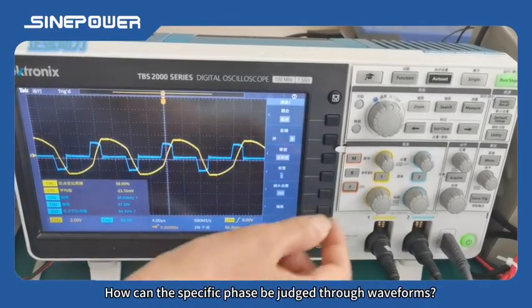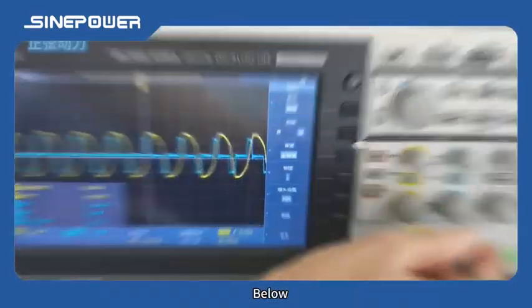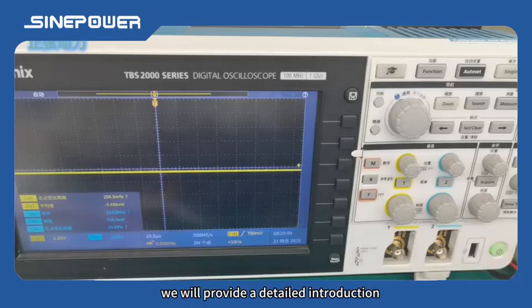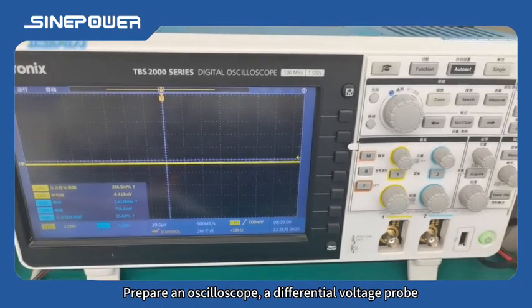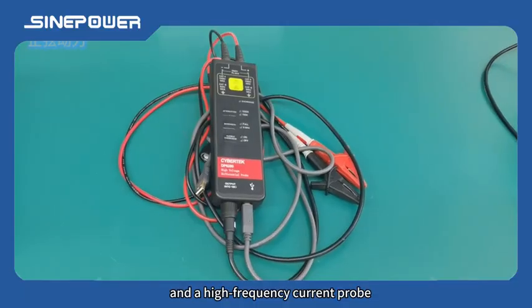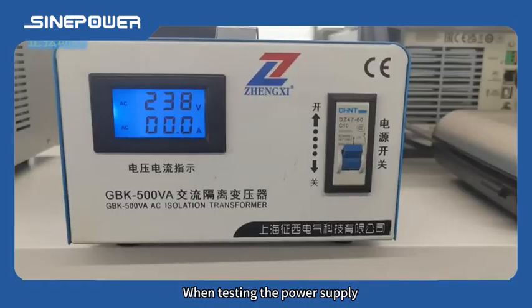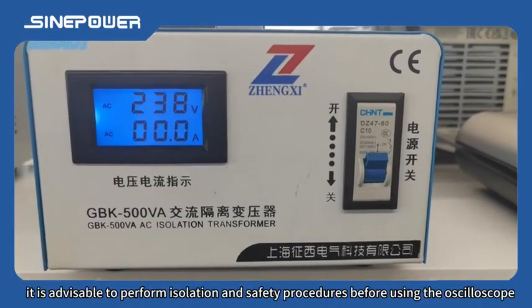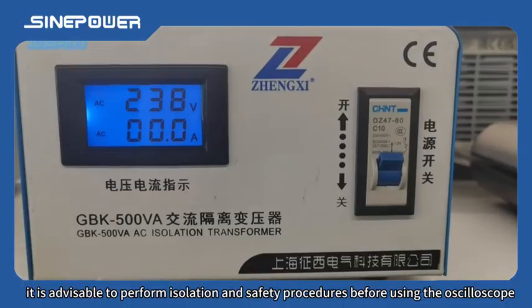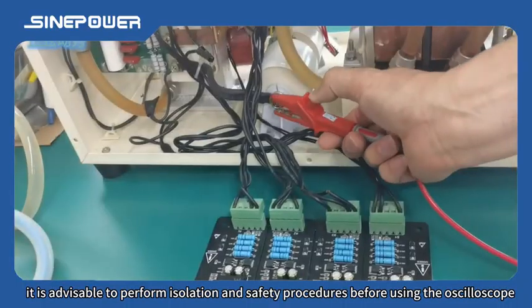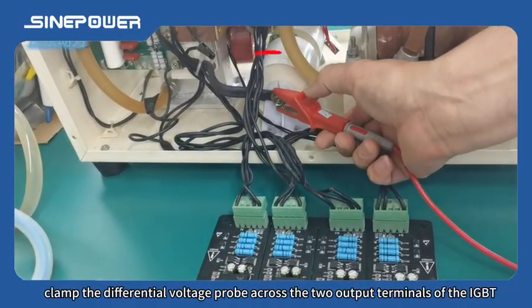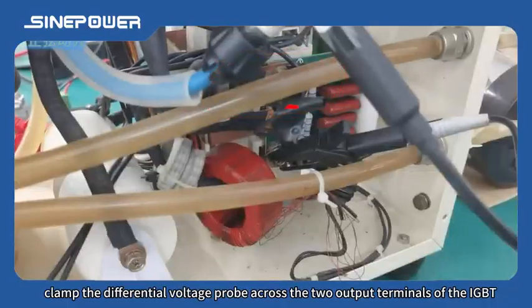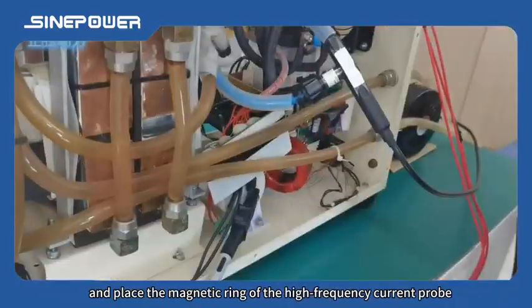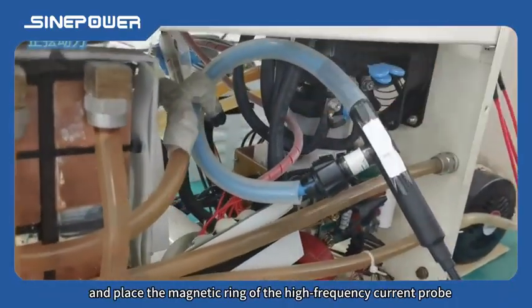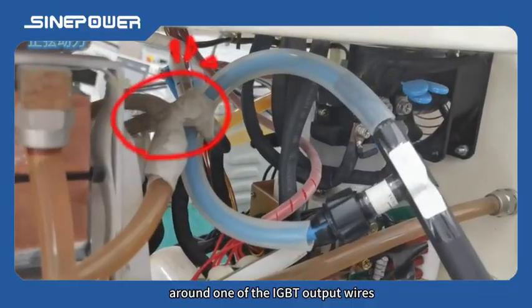How can the specific phase be judged through waveforms? Below, we will provide a detailed introduction. Prepare an oscilloscope, a differential voltage probe, and a high-frequency current probe. When testing the power supply, it is advisable to perform isolation and safety procedures before using the oscilloscope. Then, clamp the differential voltage probe across the two output terminals of the IGBT, and place the magnetic ring of the high-frequency current probe around one of the IGBT output wires.